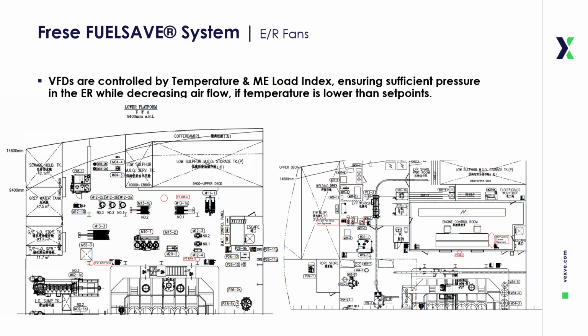Two primary control inputs are used: engine room air temperature, monitored through strategically placed temperature sensors, and the main engine load index, which reflects the vessel's current power demand. When the load index is high or engine room temperature approaches the set point, the fans are driven toward higher speeds to ensure sufficient airflow and maintain a safe working environment.